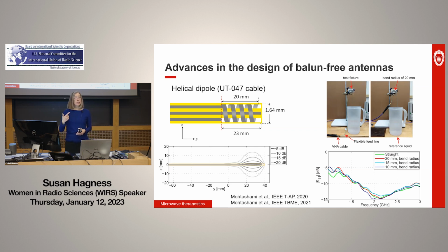The current on that outer spring, or helix—I call it a spring because we've implemented it with a spring—reverses direction a quarter wavelength away from the feed point, and ends up aligning with the current on the inner extended conductor. This creates a relatively low input impedance and chokes the current that would otherwise flow on the outer surface of the outer conductor. So without a balun and without an impedance matching network, we get a compact SAR pattern, a compact ablation zone.